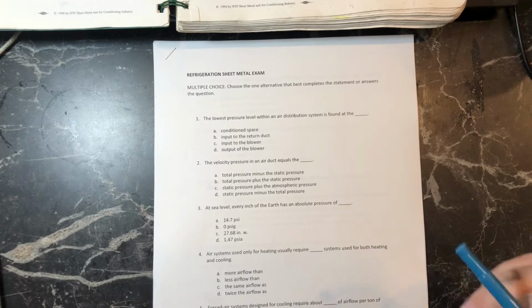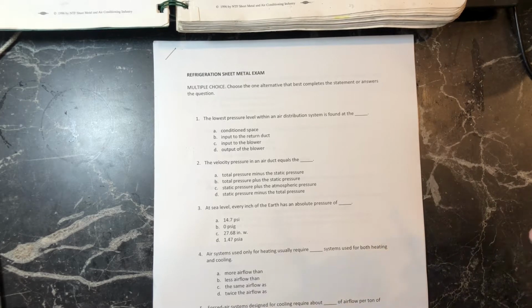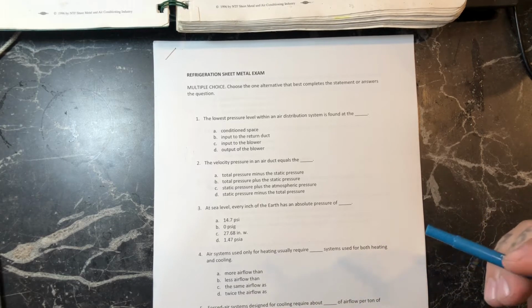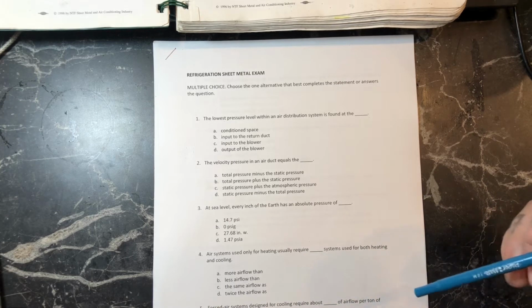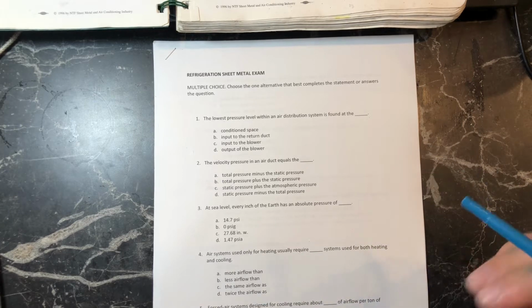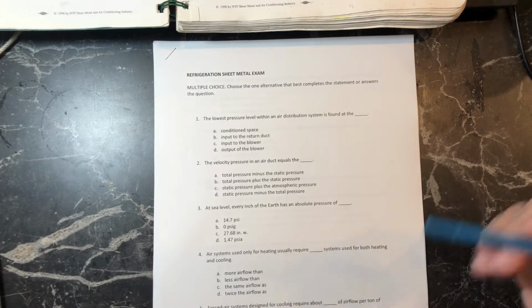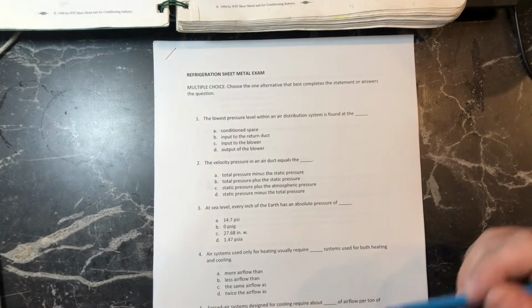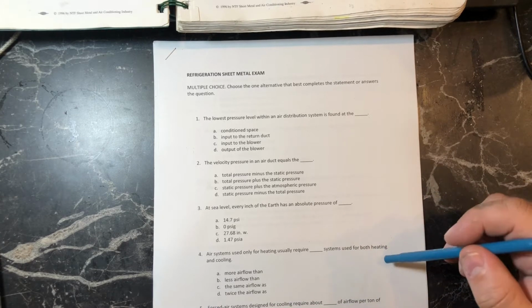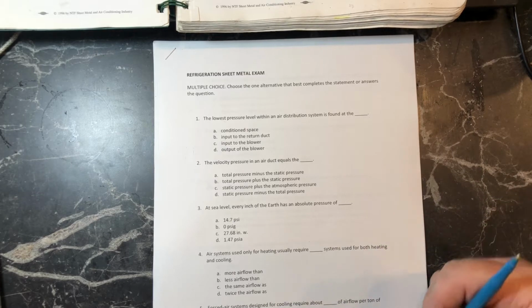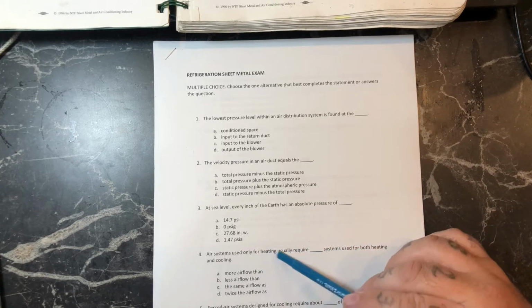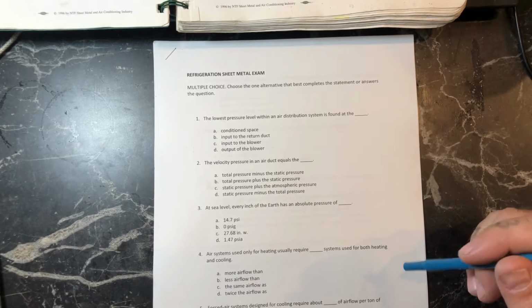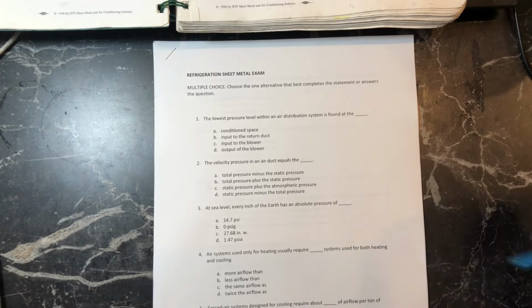If it's a gas or oil furnace, all the round supply runs that go to all the registers in the building are probably 5-inch. If you've ever seen a house done with a heat pump, where they're doing heating and cooling, the round runs typically are 6-inch, just because they have more airflow in them. One of the main reasons you want more airflow is that if you don't have enough airflow passing over that coil, it can tend to freeze up. So if a system is only heating, it's going to require less airflow than one that does both.